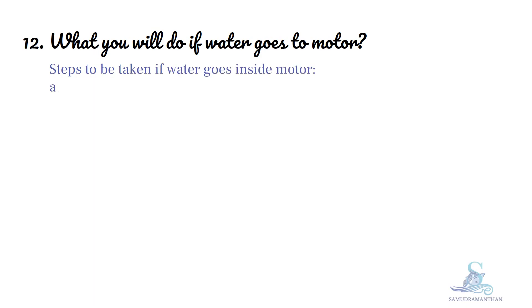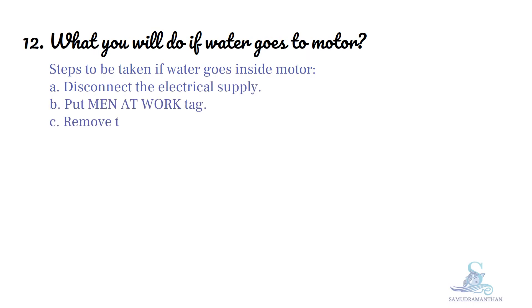What you will do if water goes to motor? Steps to be taken if water goes inside motor are: First, disconnect the electrical supply. Then, put MEN AT WORK tag. Remove the coupling bolts.